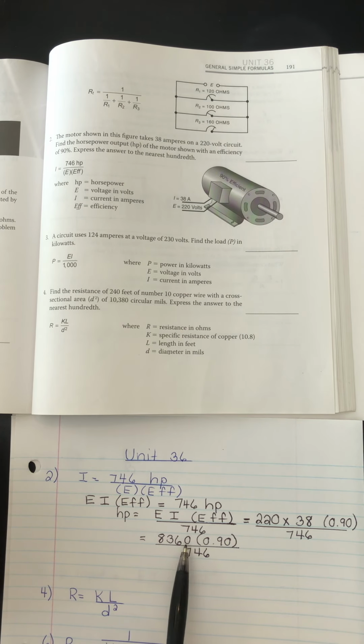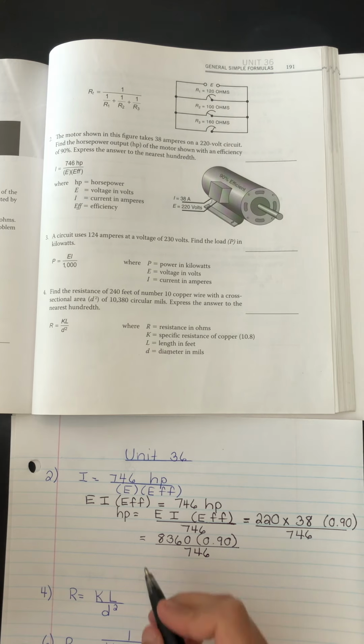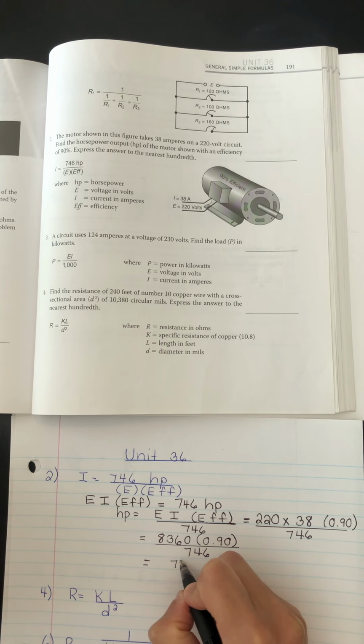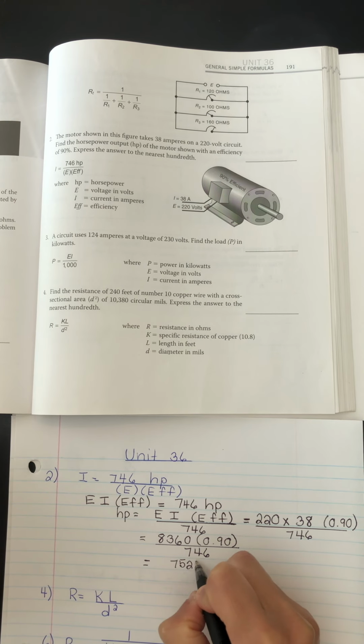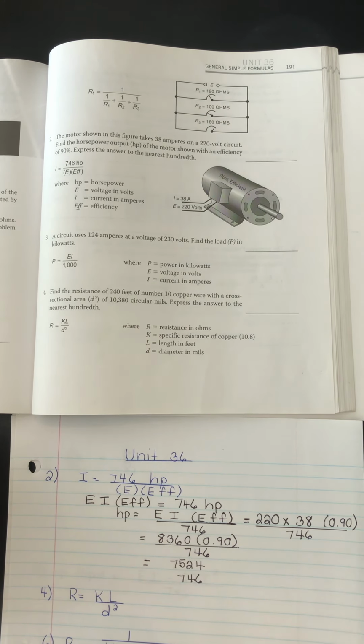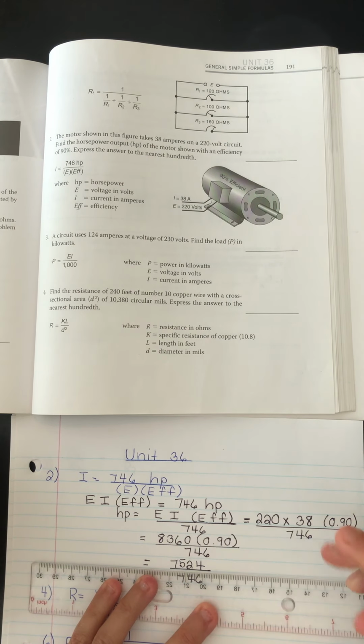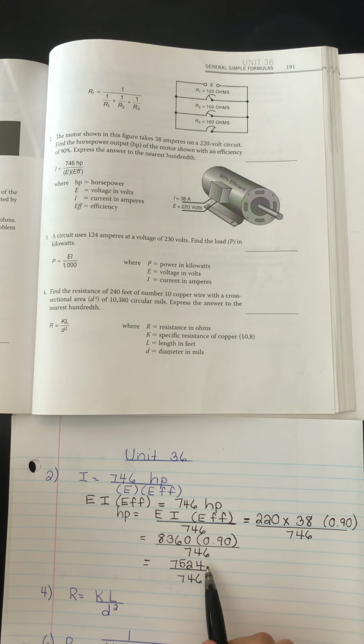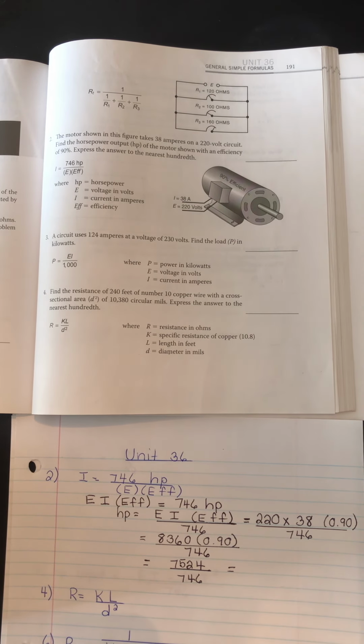Okay, now if we take that value and multiply it by 0.9, we will now get 7524. Okay, so that's 90% of the input power. So what does it represent? It actually represents the output power, again, in watts. Okay, so this value, 7524, is the output power in watts. And then finally, when we divide that number by 746, we will have the output power, but in the unit horsepower.